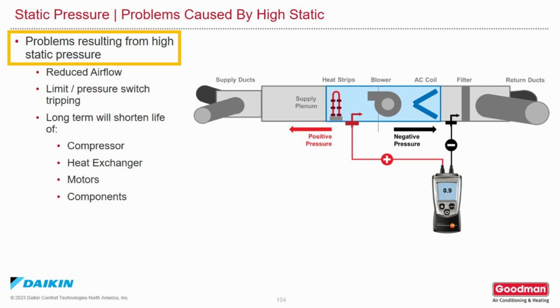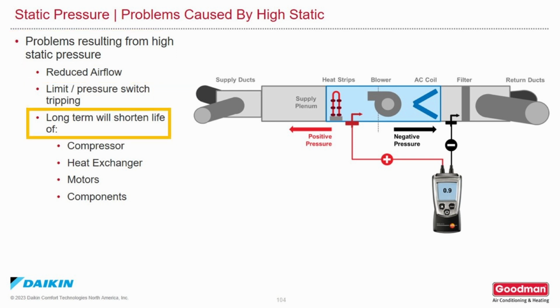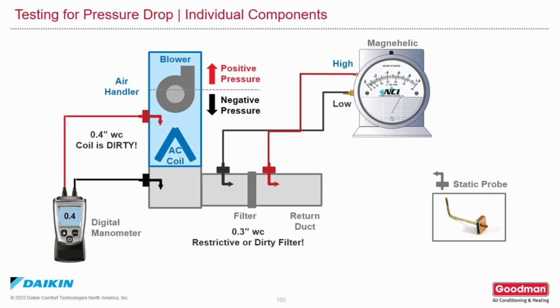Some of the problems caused from high static pressure can include reduced airflow, limit or pressure switch tripping, and long-term will tend to shorten the life of a compressor, heat exchanger, motors, and other components. You can test the pressure drop across individual components using a manometer or a magnehelic. For instance, if you have 0.4 inches of water column static pressure across the evaporator coil, the coil is dirty. If you have 0.3 inches of water column static pressure across the air filter, then the air filter is dirty.